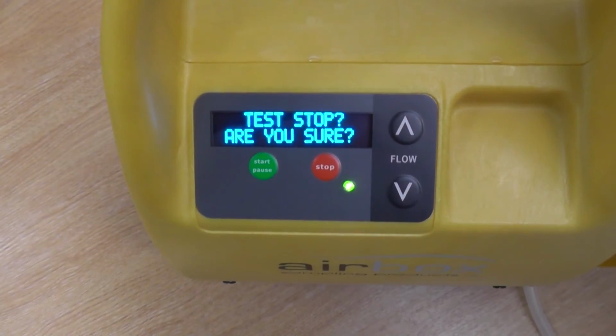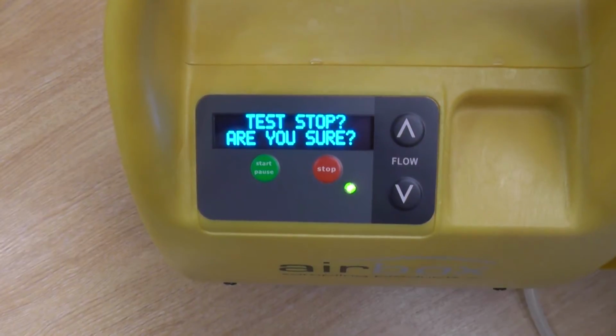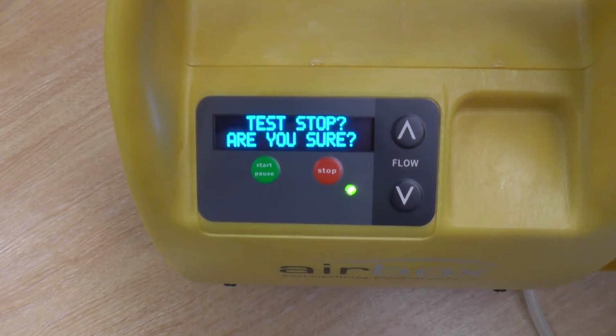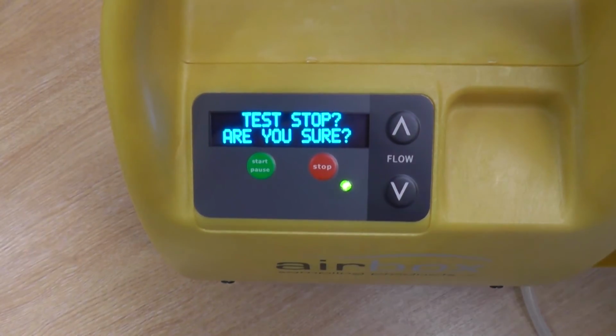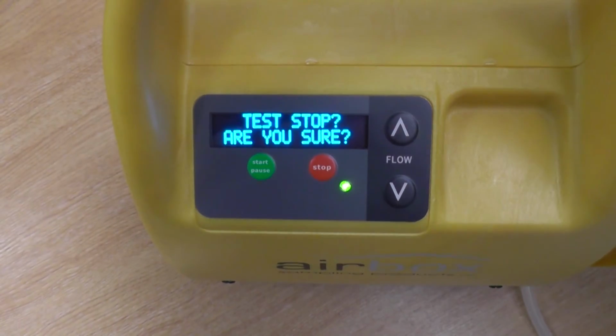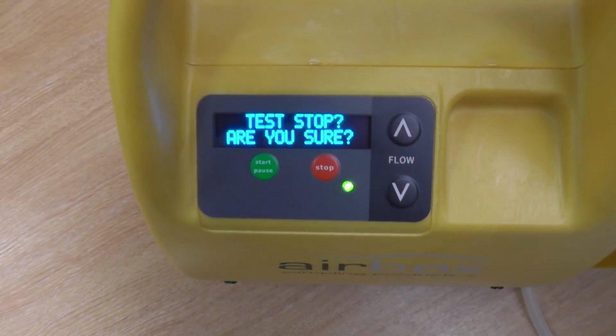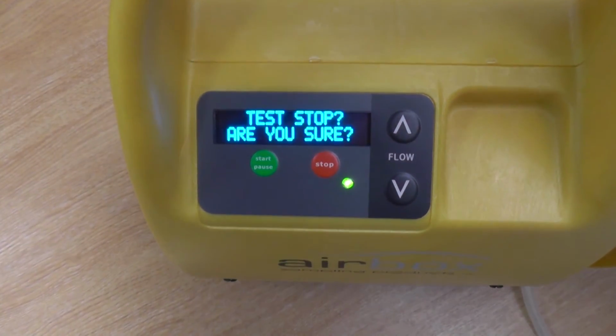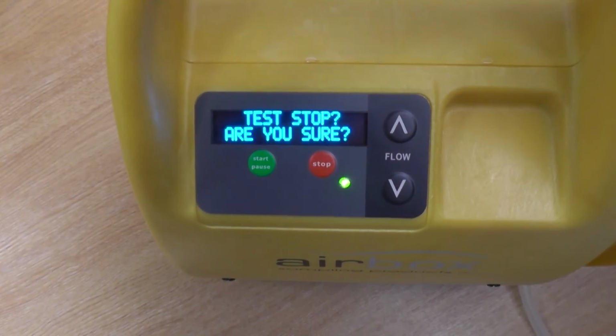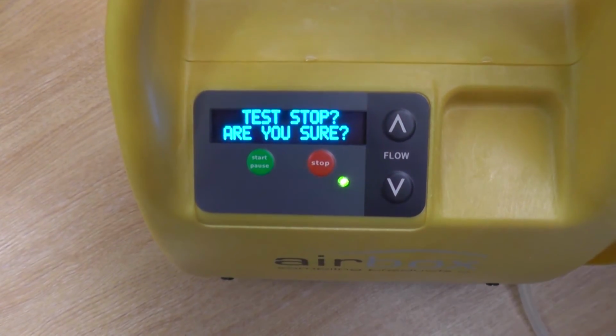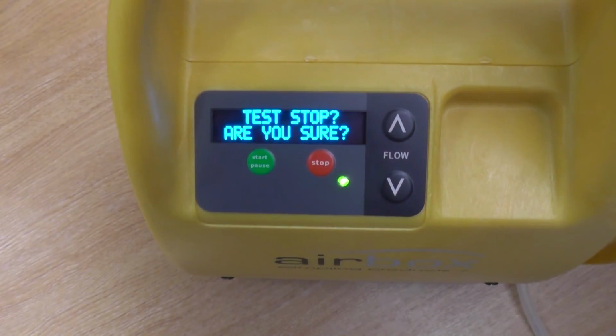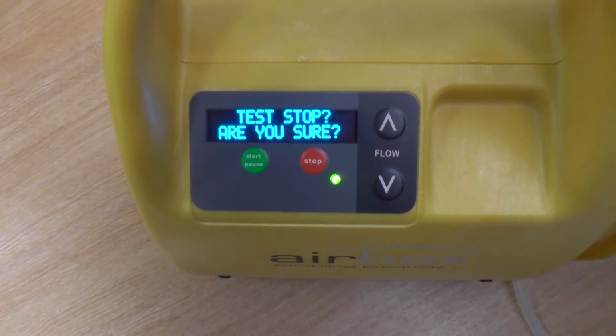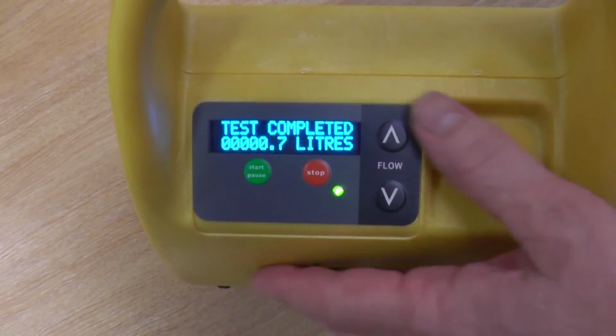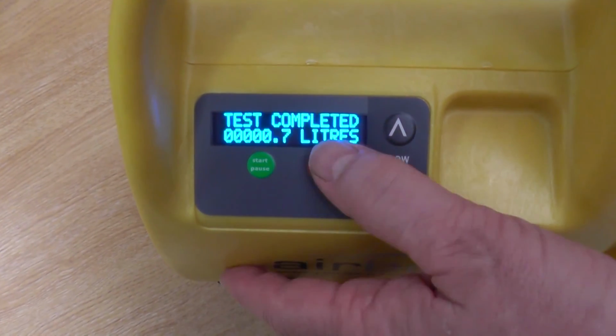But because it has a slow start for a few seconds, it'll always run a little bit longer than you originally expected, only a few seconds, unless the pump gets blocked, in which case it'll keep running until the air has been collected. Because the flow sensor is sensitive to plus or minus 5%, it'll always allow for full collection of air. If the filter gets blocked, or for any other reason the pump is slowed down, it'll continue to collect the air until it reaches the amount of air you asked it to collect. Okay, again, it'll tell you how much air you've collected. Once you finish the test, you'll be able to download the information onto your computer.